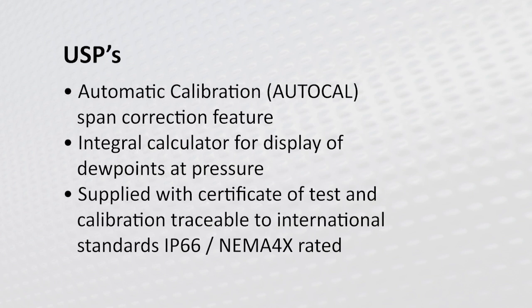Automatic calibration or AutoCal is a span correction feature, integral calculator of a display of dew points at pressure, supply of the certificate of test and calibration traceable to international standards, IP66 NEMA 4X rated.